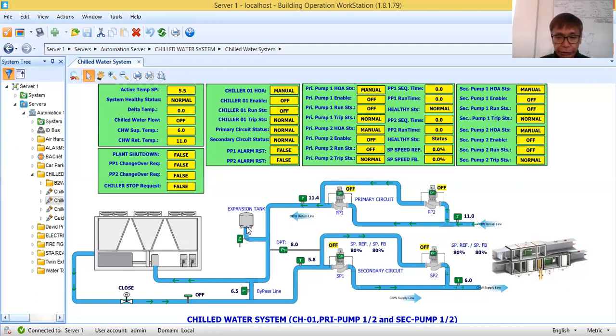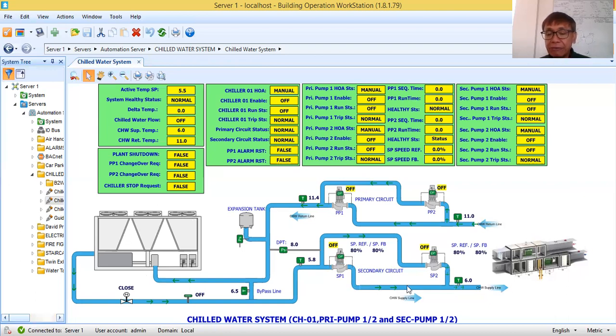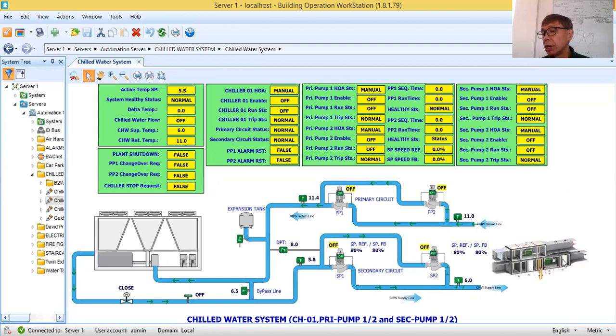The next part is the primary pump: PP1, primary pump one and primary pump two. Primary pump one and two will pull back the chilled water from the building and push it back to the chiller. The secondary pump will be the one to deliver or supply chilled water to the building.